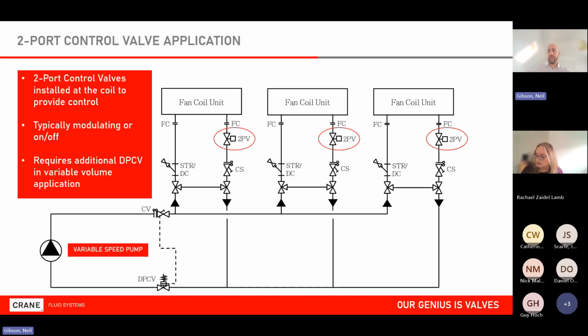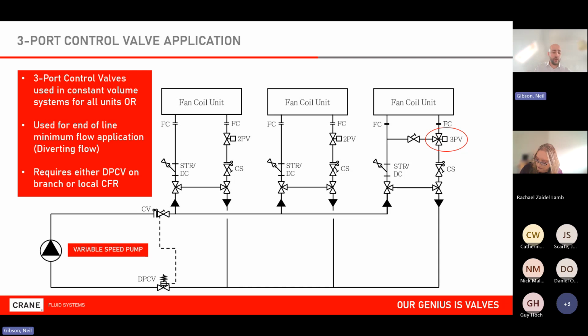Protecting the system against changes in differential pressure. All of these had to be designed in and considered. We'd also use a 3-port valve, typically either on a constant volume system on all units, or in a variable volume system, we might have one on the end of line. You can see the example there. The key part is that we want to maintain a continuous flow throughout the system to maintain circulation, minimum pump speeds, etc. So a typical application there.